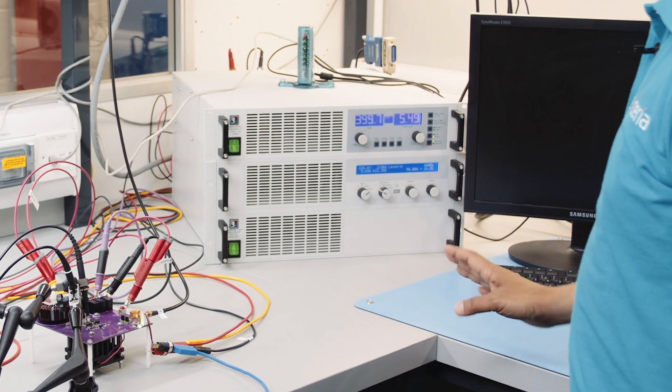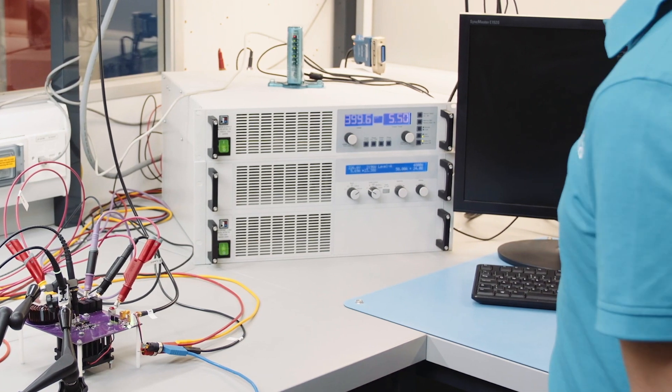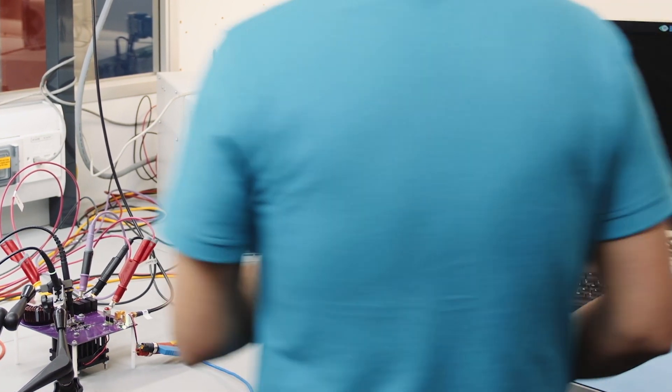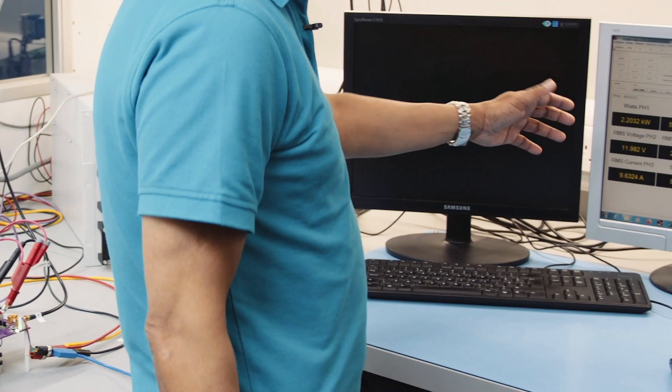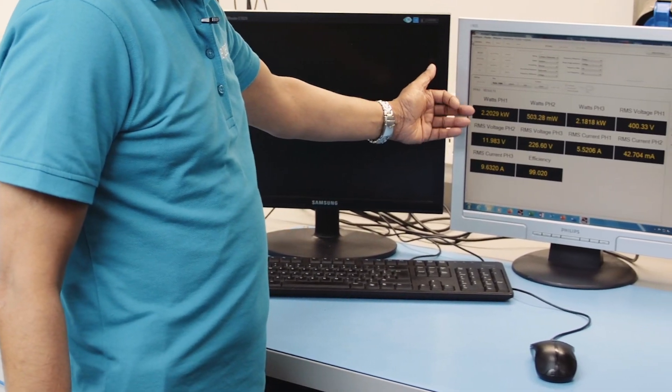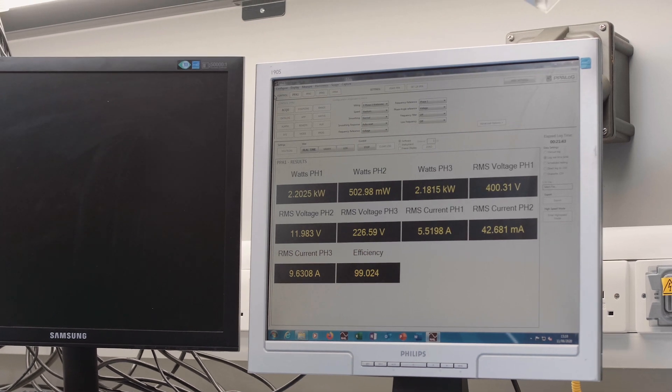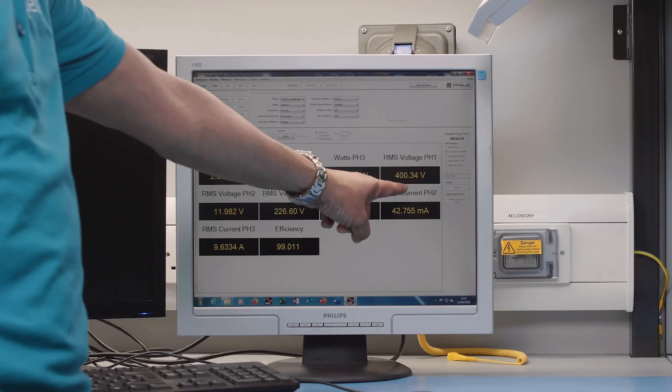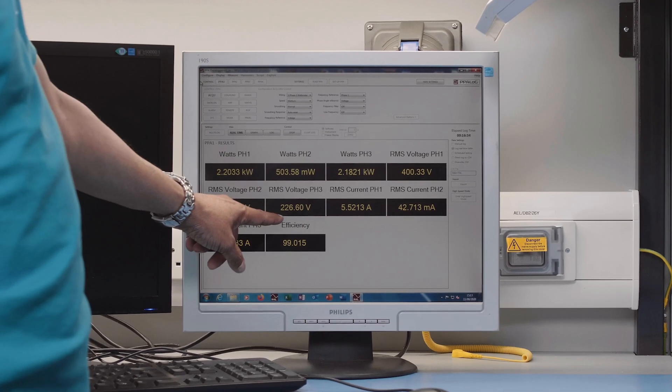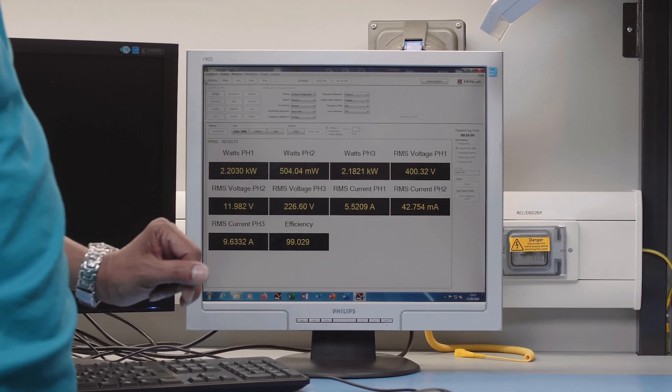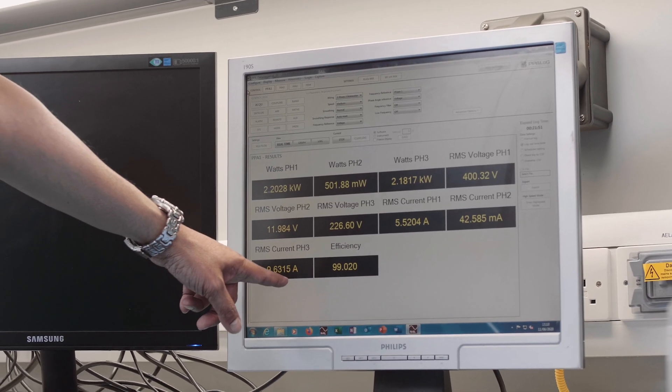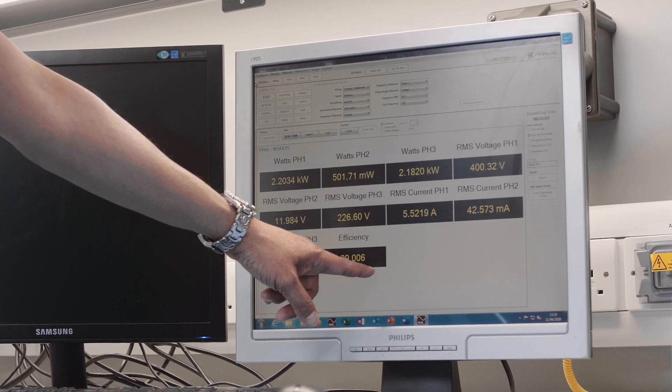This one is actually giving us the efficiency trace. We can look into this screen. You can see that there is a 2.2 kilowatt input and almost 2.2 kilowatt output with the 400 volt input and 226.6 volt output. So this is the battery load with 9.6 amps and offering 99% efficiency.